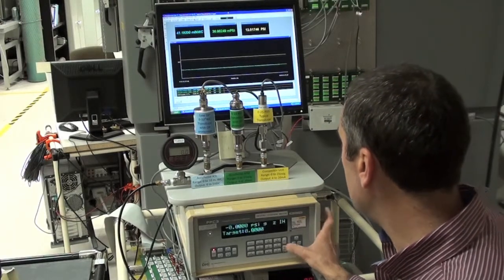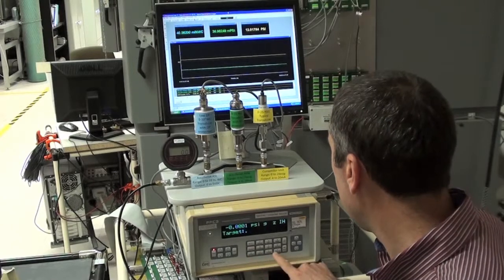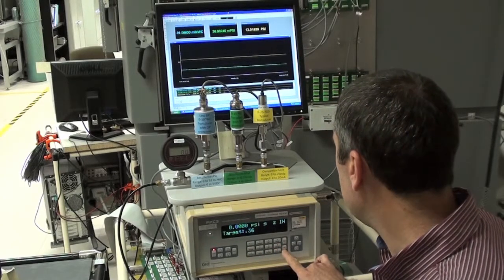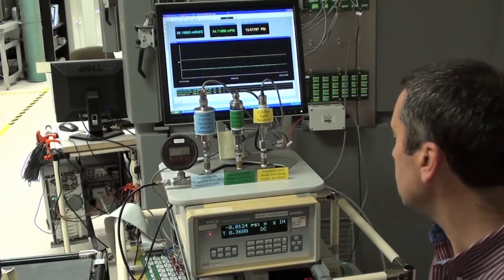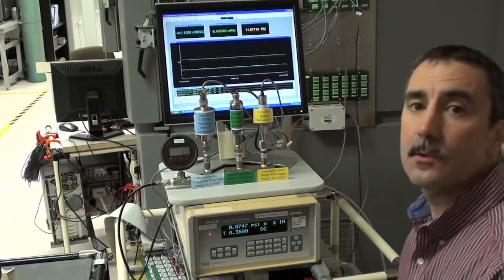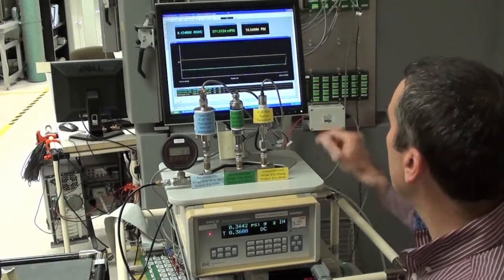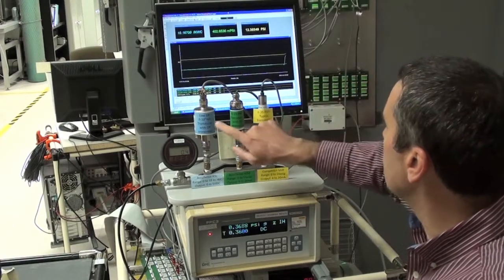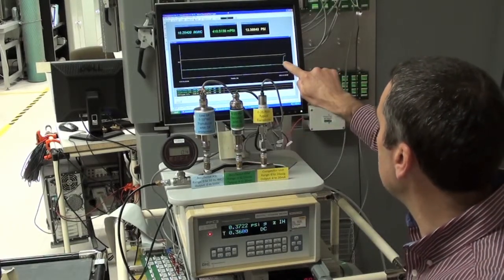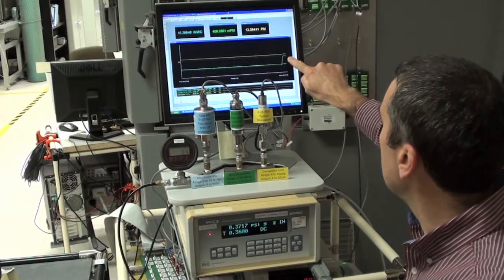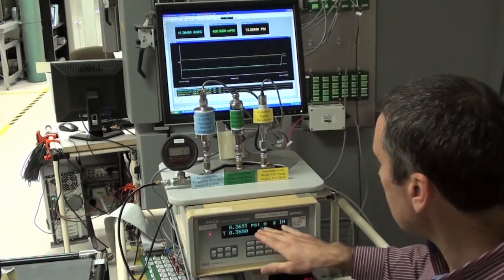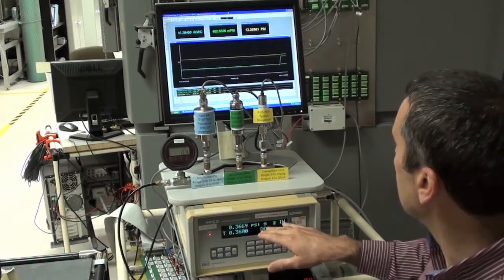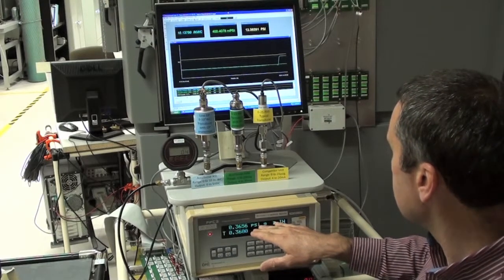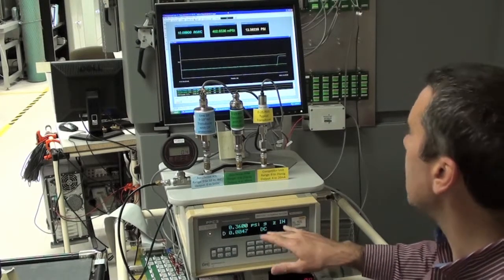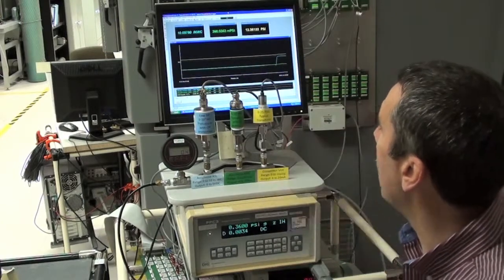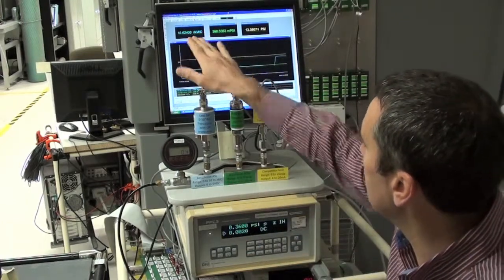So I am going to enter a pressure of 0.36 psi, which is equivalent to about 10 inches of water. And you will see the blue trace from the differential pressure transducer coming up to pressure. It's trying to stabilize. Pressure controller is overshooting a little bit. It's stabilizing now at 10 inches of water. You can see the meter reading 10 inches.